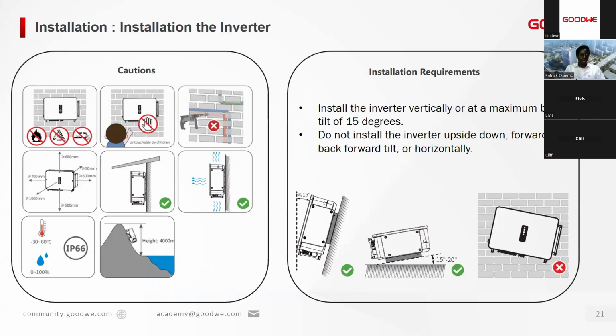Furthermore, just looking at installation, of course, we do advise you put it away from any fire or explosives. Do not touch it when it's running because it's slightly hot. Then also, wherever you're putting it, do not drill it into any pipes or cables. Another thing to consider is the spacing so that you provide proper ventilation around the inverter. As you can see from the diagram there, it's approximately 600 millimeters around the inverter.